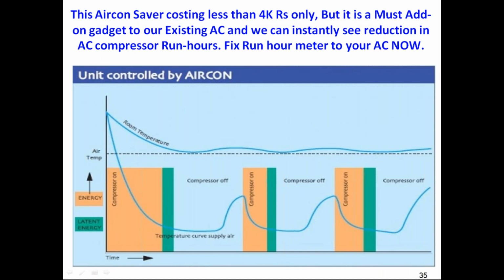In the air conditioner, what we suggest is replacing the air conditioner in one aspect. The other one is going for an aircon saver, which is a dual sensor based algorithm. One is based on the ambient temperature and the other one is at the room temperature. This is an EEPROM based microcontroller gadget, which is used in many of the industries and all the banks and offices, where they achieve almost 20 to 30%. Many of the air conditioners are all oversized, or the size is more for the given premises or for the given application. Here this aircon saver gives almost 15 to 30% energy savings based on the application. It can definitely be tried in all the building segment air conditioning. Next, please.